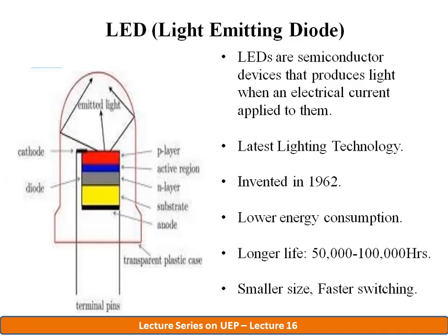As a matter of fact, fluorescent and high intensity discharge light sources cannot function without a ballast, which provides a starting voltage and limits the current to the lamp. Similarly, an LED requires a power supply, commonly called a driver. It requires a driver circuit. The line AC power is converted to the appropriate DC voltage. If we take single phase supply, 230 volts is converted to 2 to 4 volts DC for a high brightness LED. So a step down transformer is required, as well as a rectifier.